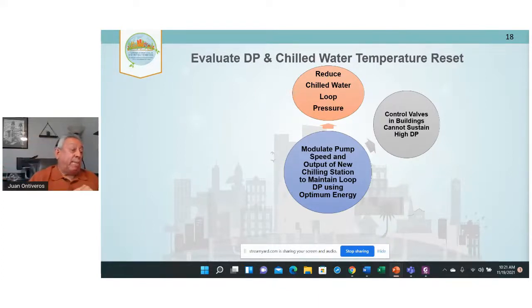So you're creating a false cooling load. It's overcooling the building. In our system, the way we offset it is we actually had to reheat it with steam and then cool. So now you have a battling system, cooling and heating battling each other. If you lower the pressure, the valve works. It doesn't get overcooled. You don't have to use the steam.